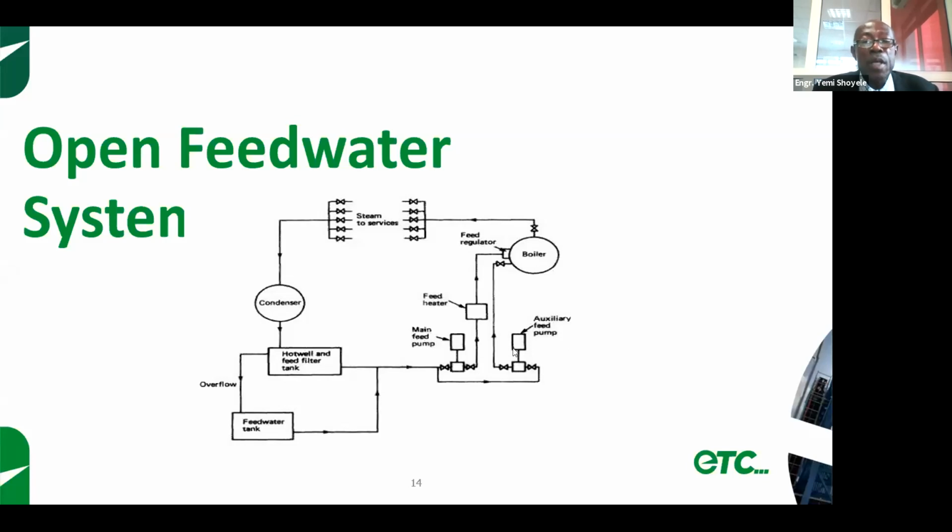Usually, for boiler systems, by law, by regulation, you have to have at least 2 feed pumps, main and auxiliary. In marine systems, it could be 3, because out there you don't have the luxury of time, and when you're in trouble, you just need to get going. So it could be 3, but the minimum is 2 by law.